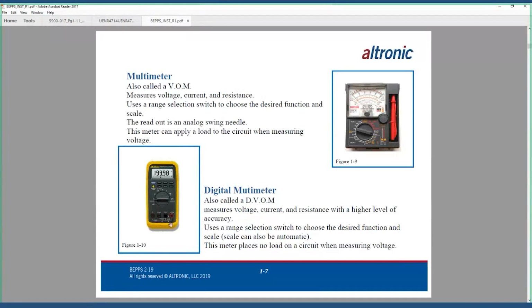And we can't see in this figure, but if you grab your meter that you use on a daily basis and start looking, it'll tell you what the fuse rating is. So keep in mind, there is an internal fuse that travels between this connection and this common connection, and this main amperage connection and this common connection. All meters are a little different. All meters have a different rating fuse on them. Most meters, when people come to my classes, we find out have a blown fuse in them, and we'll cover that as we go through the course of why.